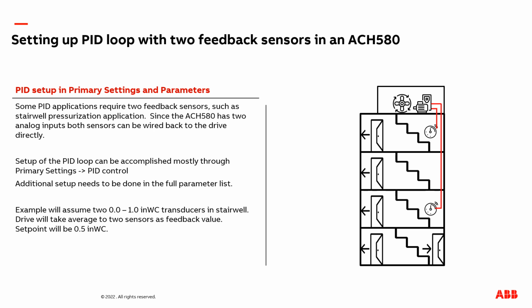The following presentation is going to discuss setting up a PID loop with two feedback sensors connected to an ACH580 drive. Now, most of the time when you set up a PID loop on a VFD, you only have to connect one transducer or feedback sensor to the drive. But there are some applications that require two sensors to be connected to the drive. The good news is the ACH580 drive has two analog inputs, so both sensors can be connected directly to the VFD.